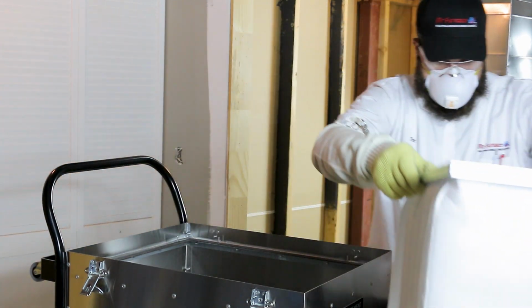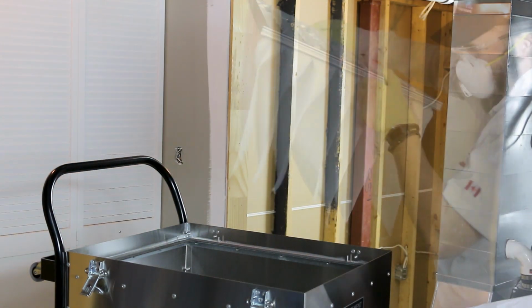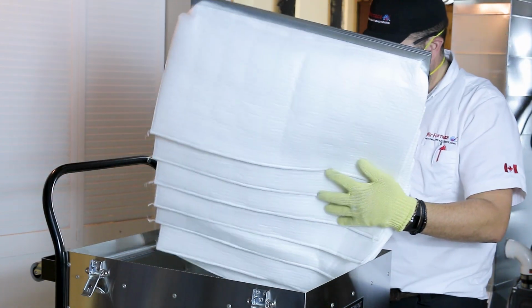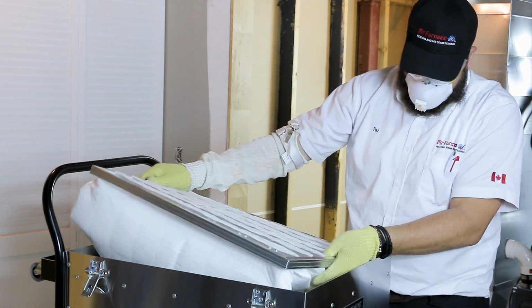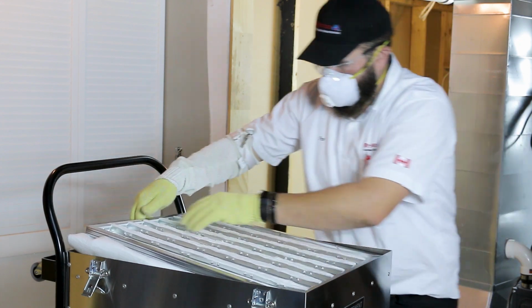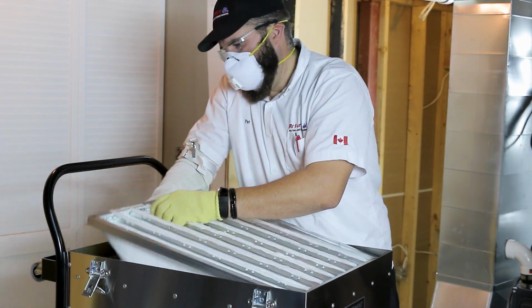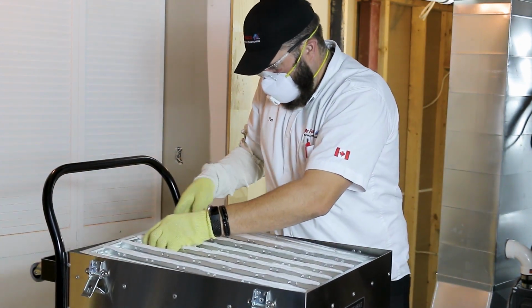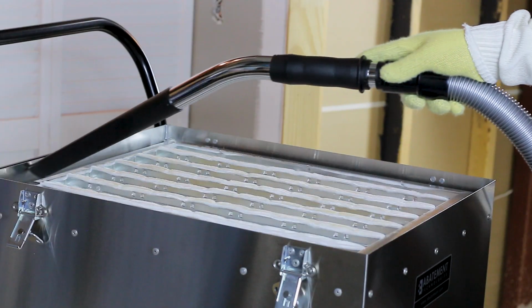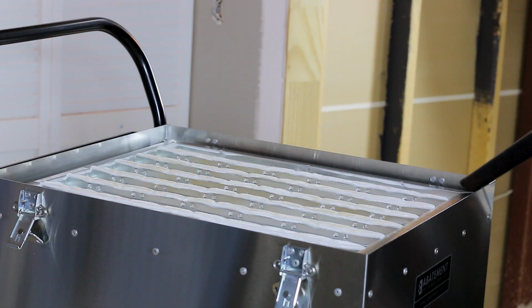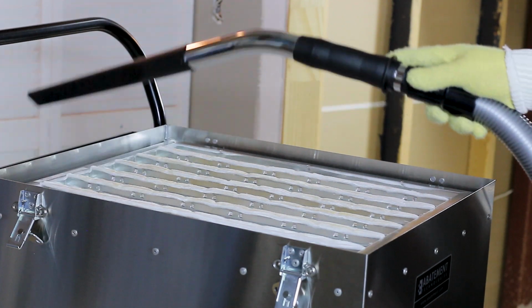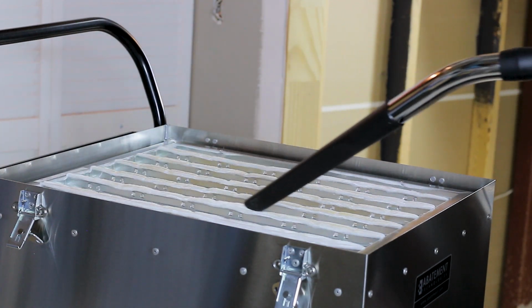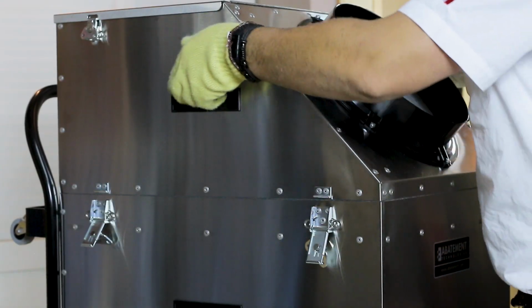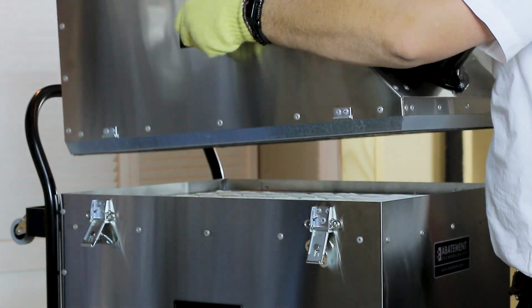If the alarm is still on after cleaning the pre-filter and the second stage filter change, or when the static pressure gauge reads around 4.5 inches of water column, then it's a good indication that the final stage HEPA filter needs to be changed. Be sure that the area between the filter frame and the vacuum edge is clean so that no debris falls into the HEPA filter when the pleated filter is removed. Most of our customers report 8 to 40 hours of use before having to replace this pleated filter.